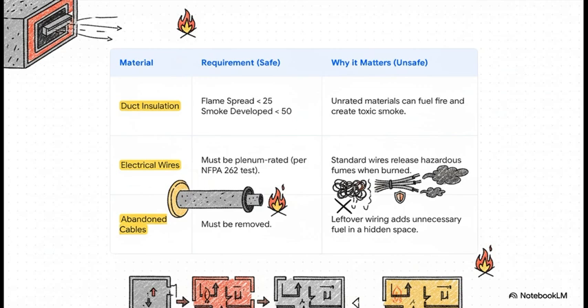That's why NFPA 90A has incredibly strict rules for everything that goes inside this critical airspace. Materials are rated on how fast flames can spread across them and how much smoke they create. Everything from the insulation to the coating on electrical wires has to meet a low smoke, low flame standard. Regular old PVC cables? Forbidden, because they release toxic fumes when they burn. Instead, you need special plenum-rated cables. The standard even makes you remove old abandoned cables because they're just sitting there acting as extra fuel waiting for a spark.